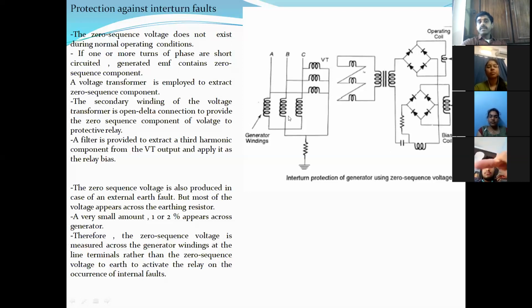So you can see here there is a generator voltage, neutral to ground connection. When there is a turn to turn fault, the zero sequence voltage will be extracted through the VT. Here you can see the secondary winding of the VT is open delta connection. This is to provide the zero sequence component of the voltage to the protective relay. Here you can see the operating coil, the bias coil, a filter circuit, and the rectifier bridge. Why are the rectifier bridges required here? Because the signal we are taking is AC. To give that signal to the operating coil or bias coil, it should be converted.